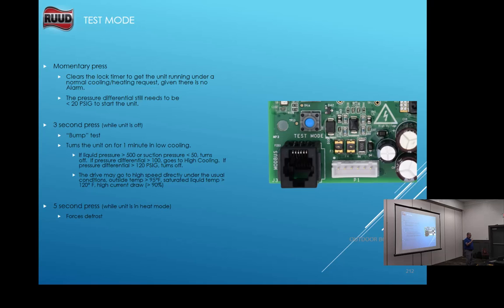Correct. You can come in here and press it for 3 seconds, and it'll do a bump test. The system will come on and run for 1 minute and go through all the parameters to make sure that it will run correctly. Defrost, if you hold it down for 5 seconds, you can force a demand defrost into the system. So you hold that button down for 5 seconds, and it will go into demand defrost. Okay?